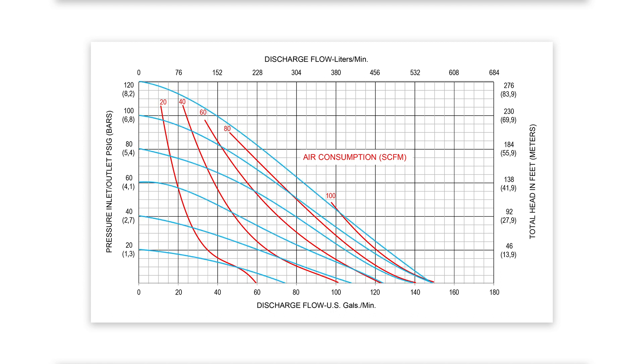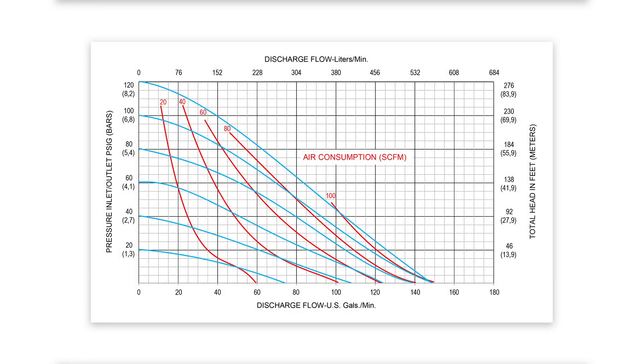There are three main pieces of information an AODD pump performance curve can define: the AODD pump's overall operating range, the AODD pump's performance, and the AODD pump's air consumption. The operating range is the minimum to maximum gallons or liters pumped per minute, identified by looking at the horizontal axis data range as well as considering the air inlet blue curved axis.